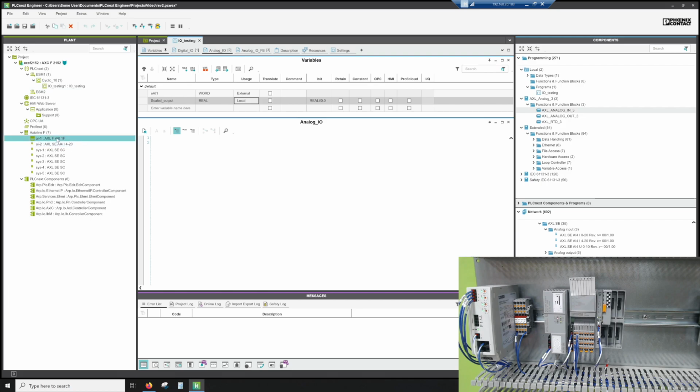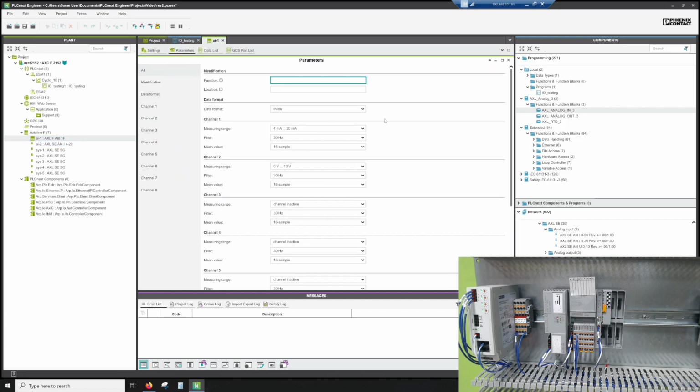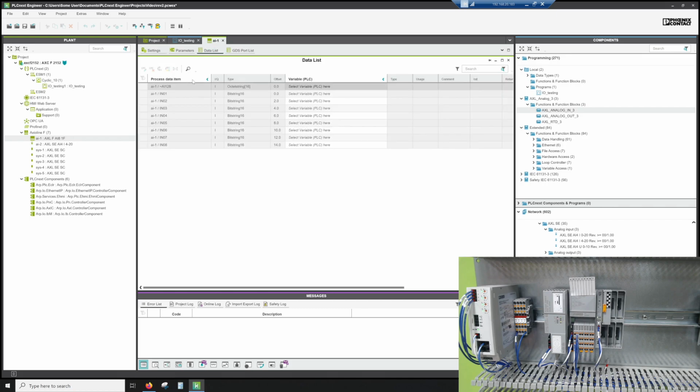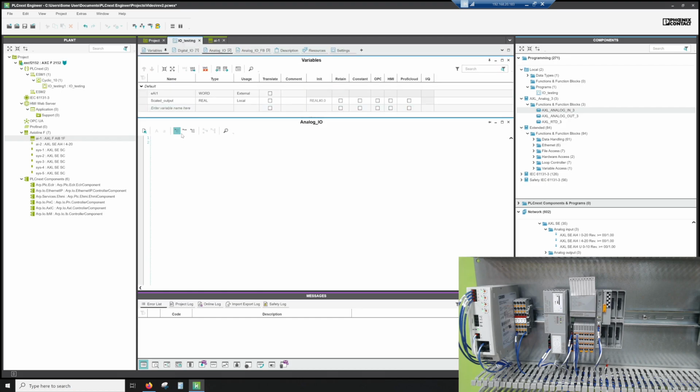So we can go ahead and just double check our AI8 card. We do see we're in the IBIL, which is the inline format, and channel 1 is set up for 4 to 20 milliamp. So if we go to the data list, we can attach to input number 1, we can attach our EAI1.